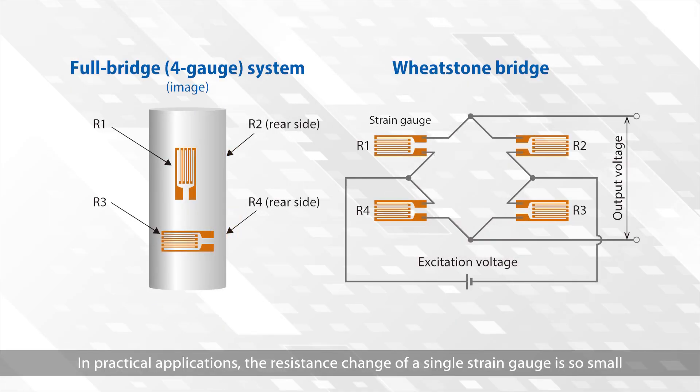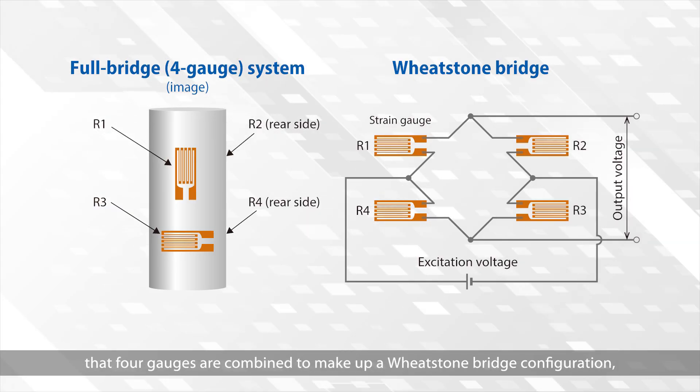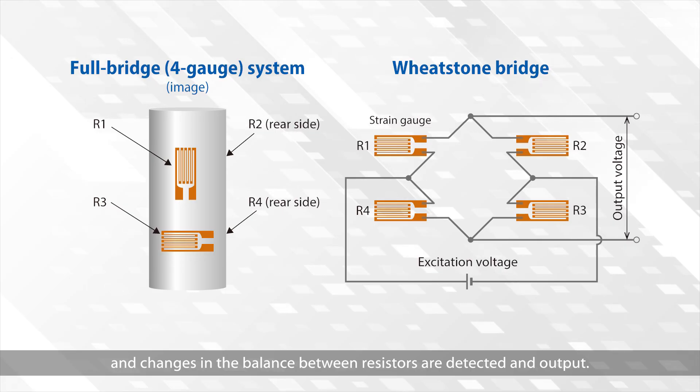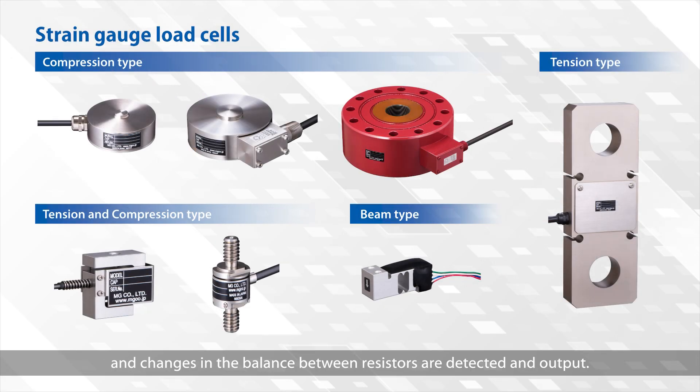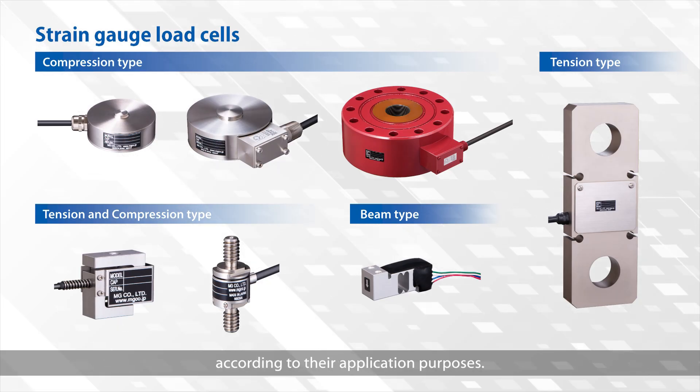In practical applications, the resistance change of a single strain gauge is so small that four gauges are combined to make up a Wheatstone bridge configuration, and changes in the balance between resistors are detected and output. Strain gauge load cell products are available in different shapes and constructions according to their application purposes.